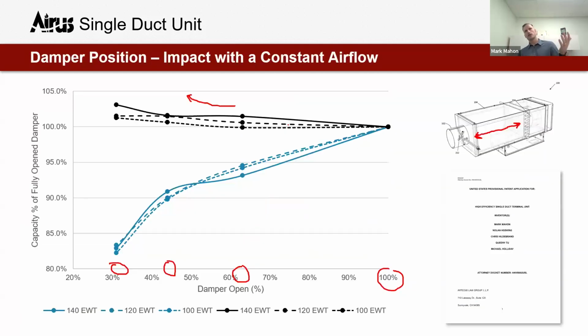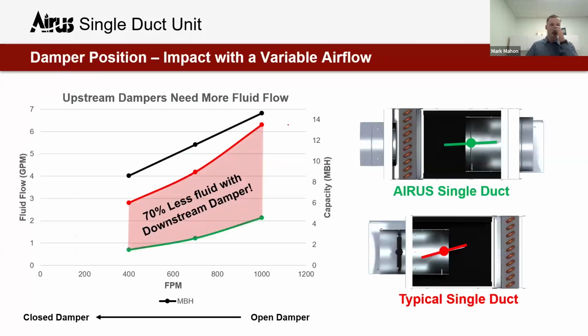So this last graph was looking at a constant airflow, but we also went above and beyond the scope of the testing from that CBE study, because I really wanted to look at this in a more dynamic, real world operation. What I wanted to see was, how is this going to work with a variable airflow rate? Because the truth is, 50% reheat to 100% maximum cooling, that means the damper is going to be partially shut already. And what about part load conditions where we expect that airflow to reduce to 40 or 30 or 20%? How's that going to influence the greater operation of the product in this case as well?